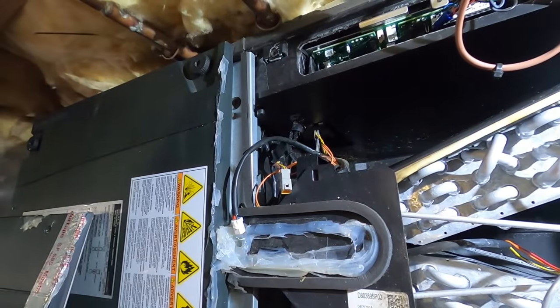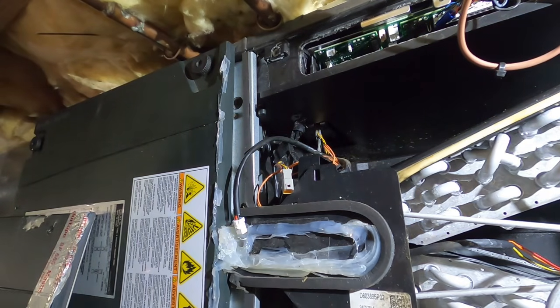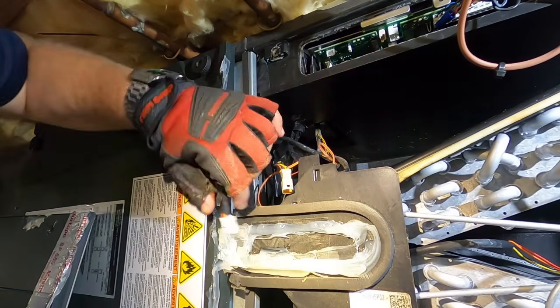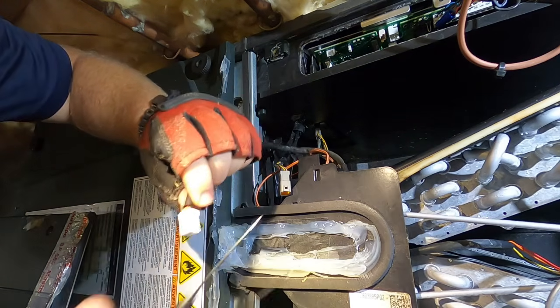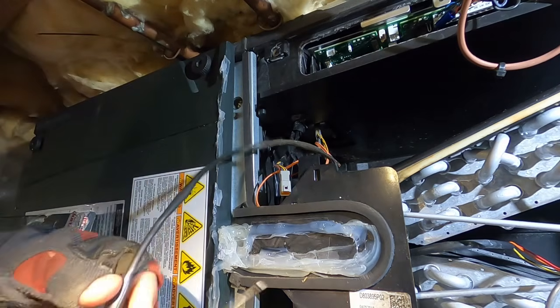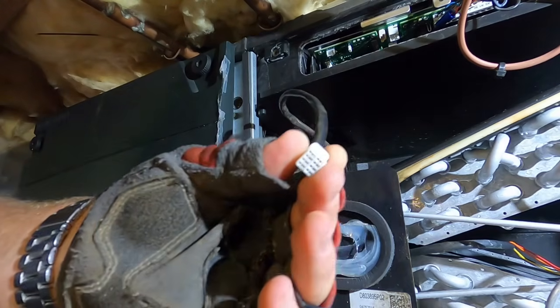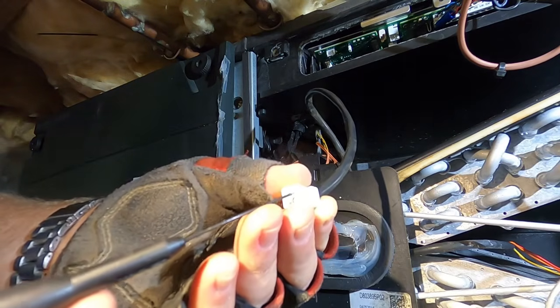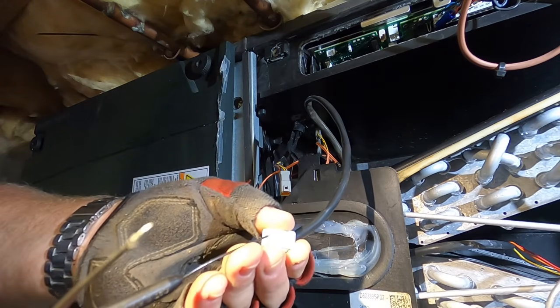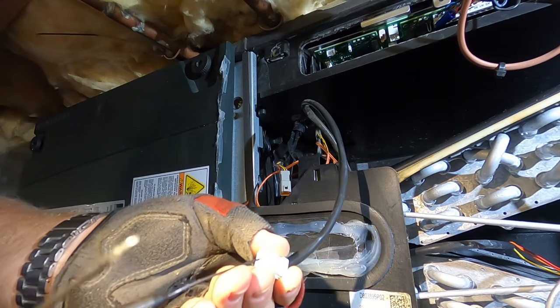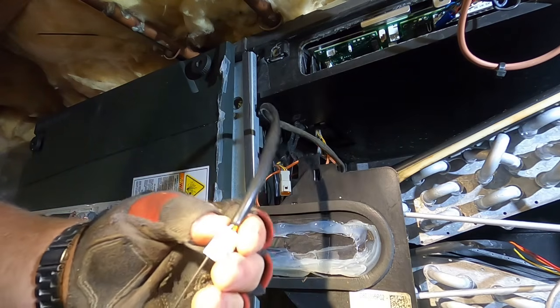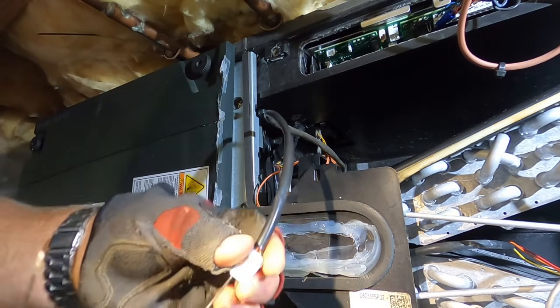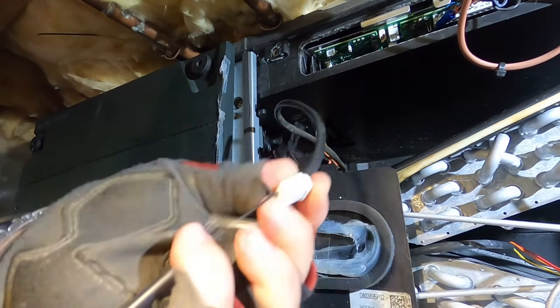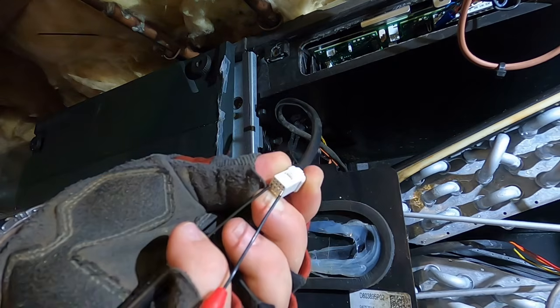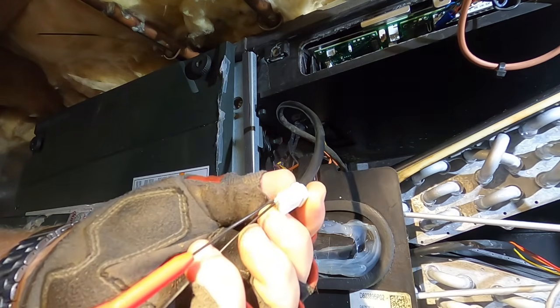So I'm going to set myself to ohms. In this situation, I'm going to turn it off, because the thermostat had reset, and the blower was starting to come on, and the annoying air noise. So I'm going to stick one of my leads in here on the gray wire. These holes are kind of tiny. Trying to get the wire to go up in there. So there we go. And then you're simply just going to ohm it out against all of these other four wires.